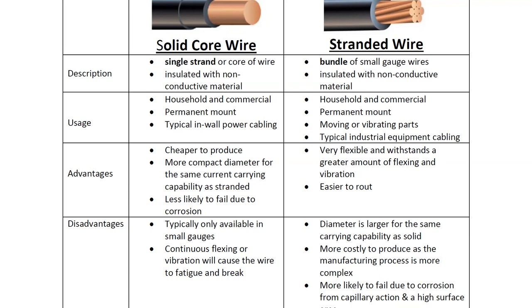So for example, gauge 14. Gauge specifies the thickness of the conductor. Sorry, I keep saying cable, but a cable is a bunch of conductors enclosed in a jacket. So when we're specifying the ampacity, for example, gauge 14, which is the thickness, and gauge, we'll talk about that, it's AWG, American Wire Gauge. When you see AWG, you just read it as gauge. And there are different numbers for different thicknesses. There are standards, right? In Europe, you would have the cross section in millimeters. In North America, we're using gauge, and sometimes you're going to be asked to specify things one way or the other.